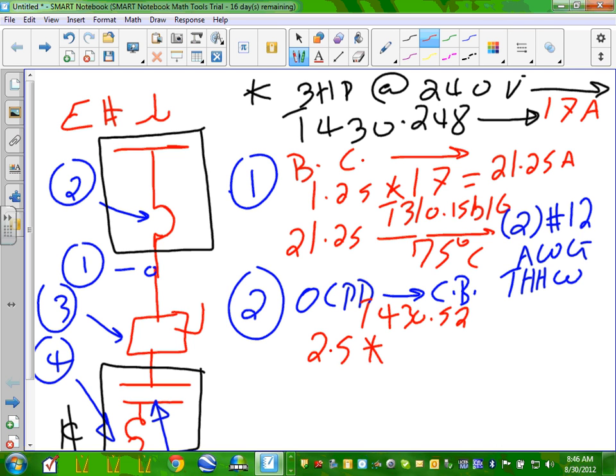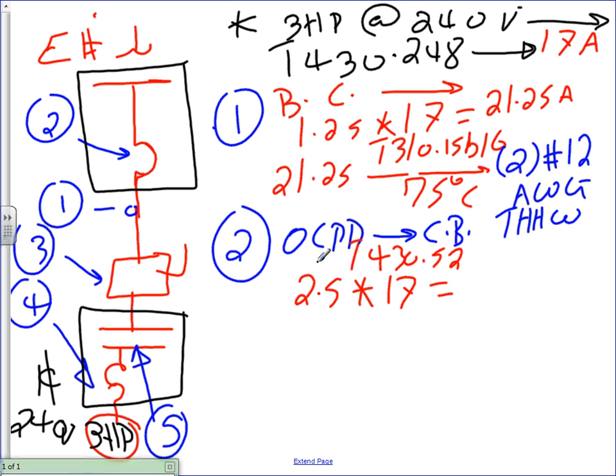Okay, so let's go do the math then. 250% multiplied by 17. I need two gentlemen to agree on one answer. 42.5 amps. Okay, you have two options. Go to the bar, drink and cry because they don't make 42.5 amp circuit breakers, right? Or custom design it yourself, pay an arm and a leg, and custom design 42.5 amp circuit breakers. Square D will be more than happy to do that for you. Or the code allows you to go up.